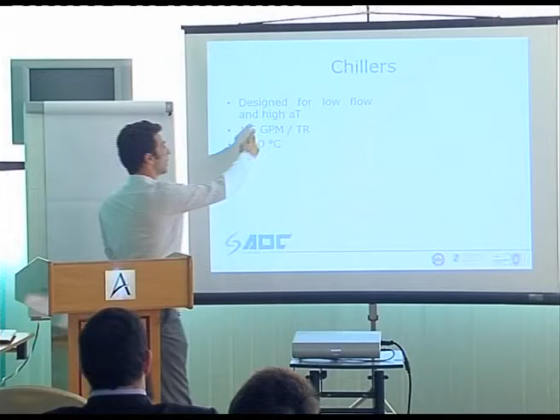Chillers in district cooling plants are vapor compression cycle. They use 134A, 123, or even ammonia. Gallons per minute, and it can be US gallons or imperial gallons. This is the delta T - it should be in Kelvin because we're talking about the temperature difference.